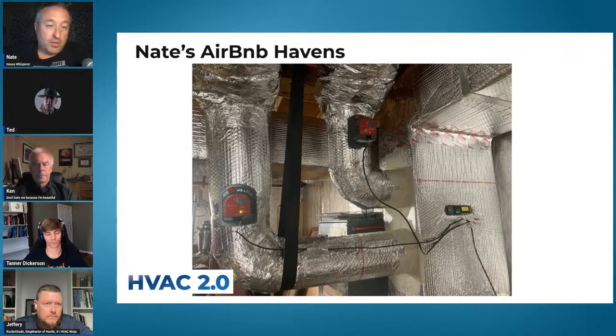When I put this in, they didn't have any controls yet for dampers. So I told one that it was a dehumidifier and said open if the humidity is above 15%, which in our climate it always is, so I just made it be on all the time. Then the other one I set to turn on whenever TVOCs came out of normal or low levels. That did the job.